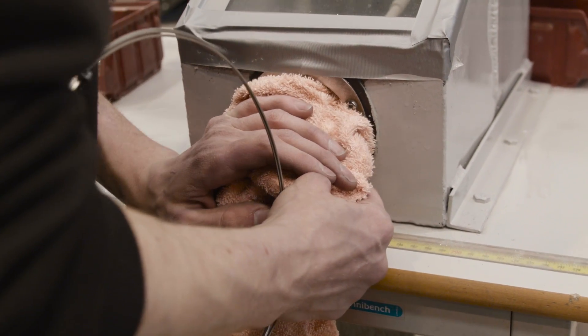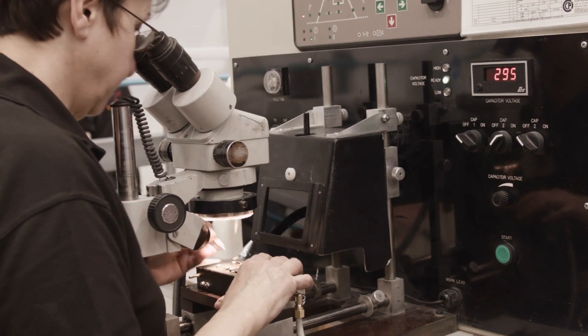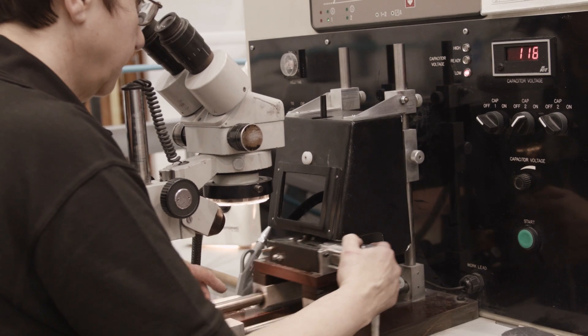The cable is then heated before welding to remove any moisture. The thermocouple hot junction weld is made under an argon shield giving a clean central thermocouple junction.